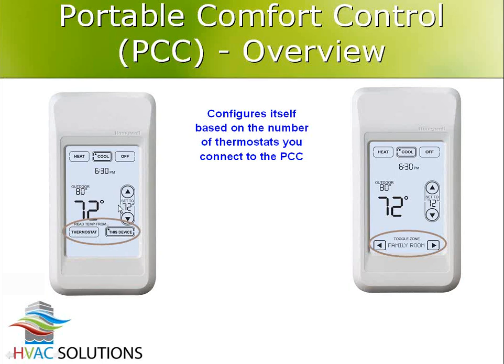You could also have it actually be the temperature sensing device. So you could tell it, I want to control to my thermostat, or I want to control to my handheld device. And now my handheld device is the temperature reading. So in this case it says it's 72 in the room. That's the number that gets fed over to the thermostat to make decisions based on, instead of whatever temperature that thermostat is reading.